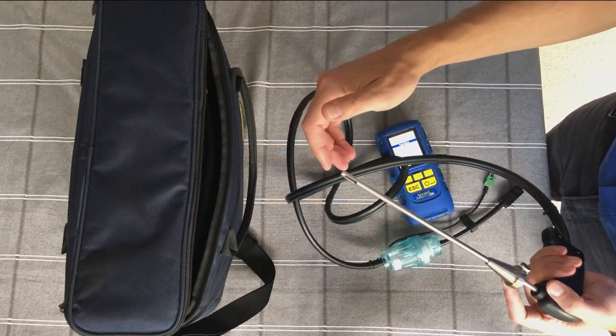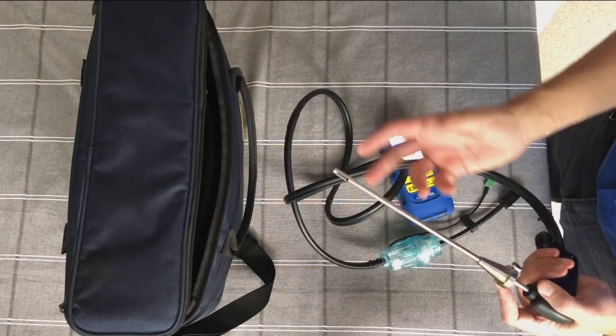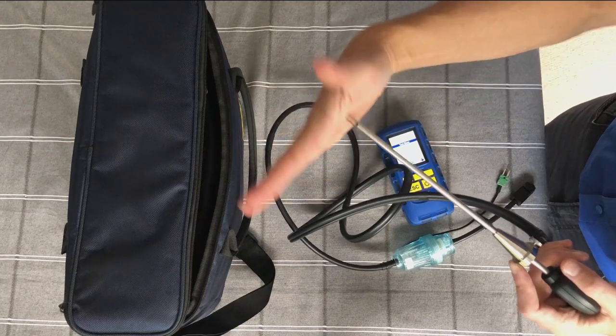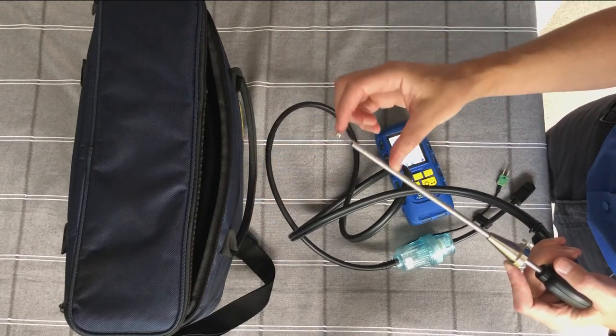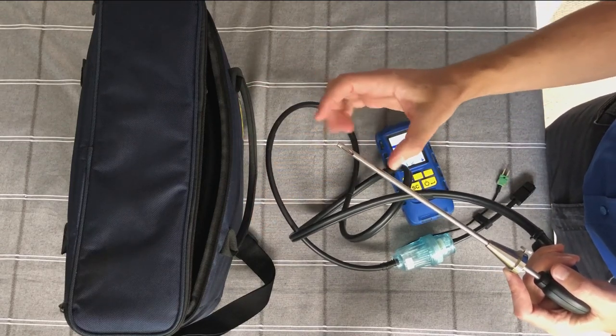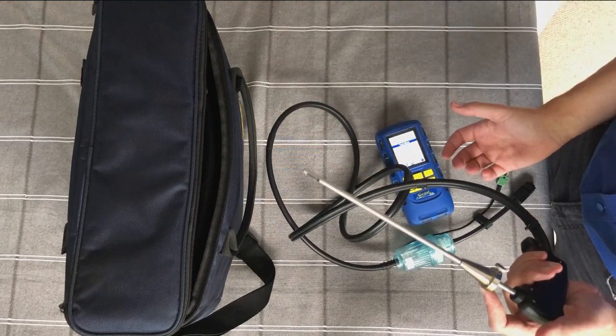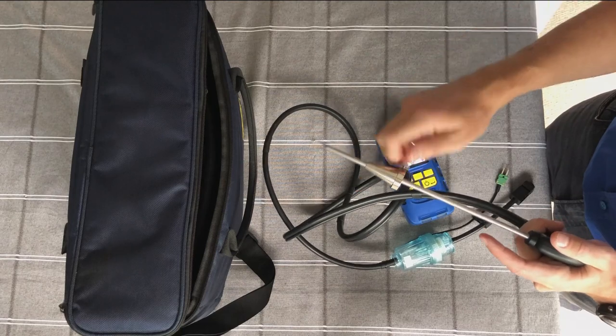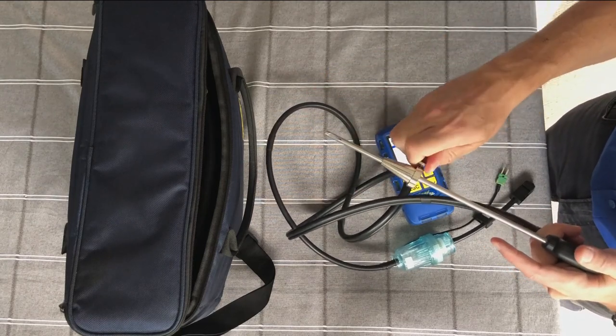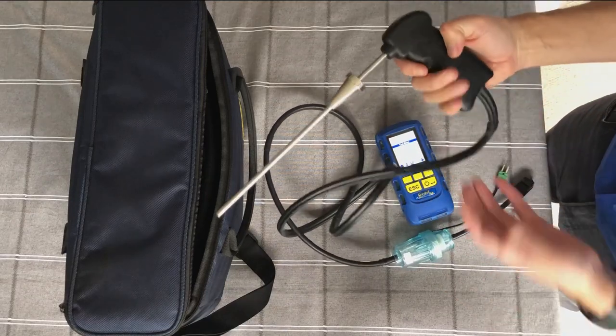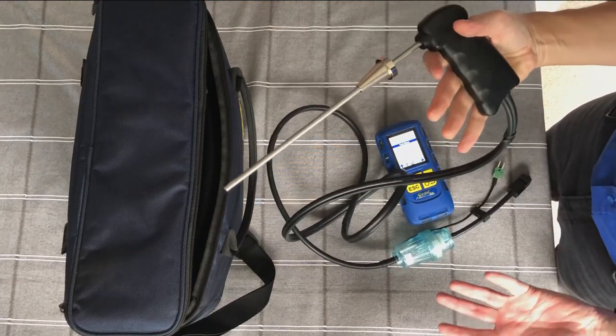You'll still get flue gas if you hit the other wall, but you'll effectively end up with a lot more condense collecting in your condense trap than is necessary if you've got it banged up against the inside wall. So try and keep it somewhere in the middle of the flue to take a gas sample rather than sucking water in. But yeah, your depth gauge will help you adjust that and hold that in the right position. There's a little dial on there to slide that up and down and lock it in place. Other than that, it's got a nice little handle.